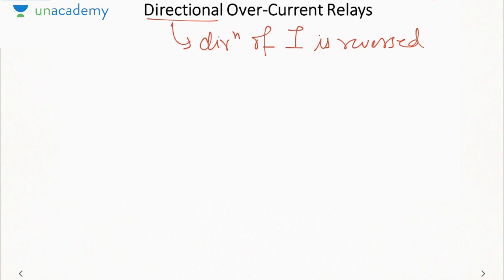Okay. So how can I say that the direction of current is reversed in case of a fault? I showed you an example in the directional relay. Otherwise, what you can understand is, whenever we use a synchronous motor in a faulty condition, then what happens?